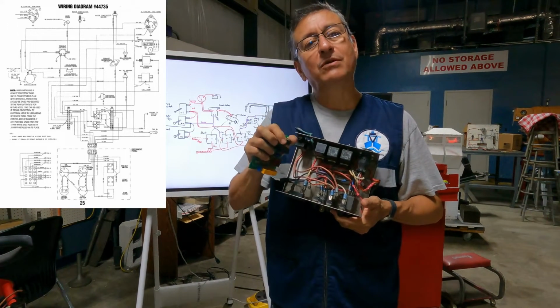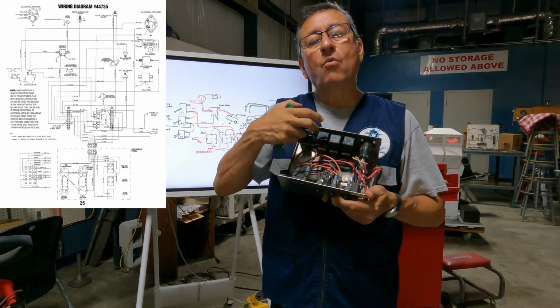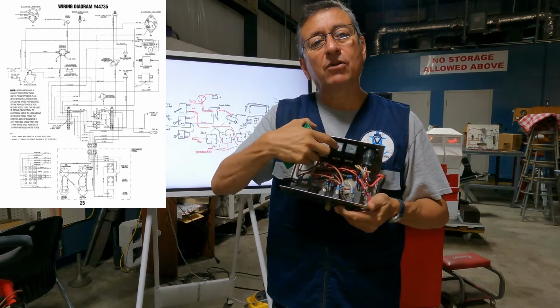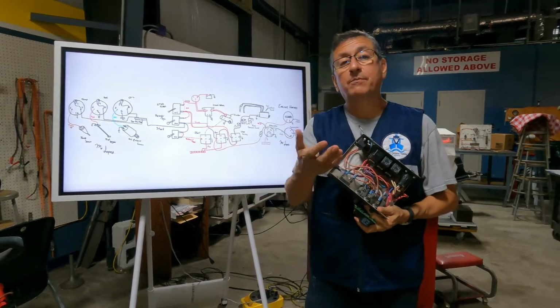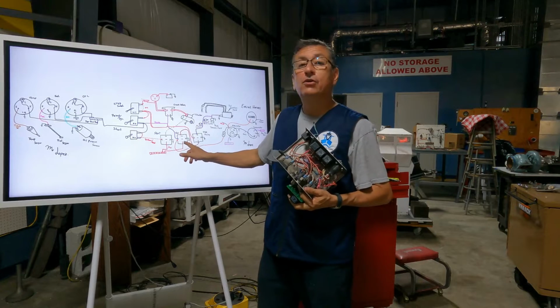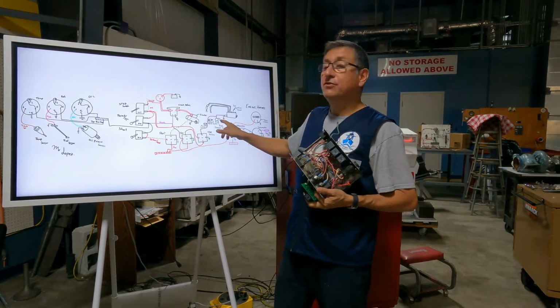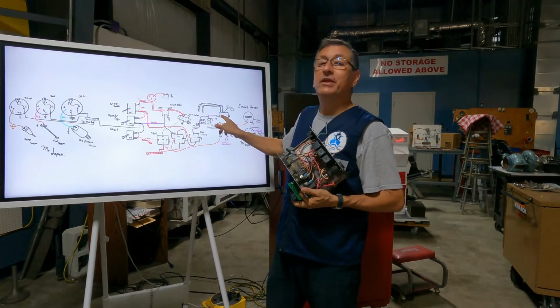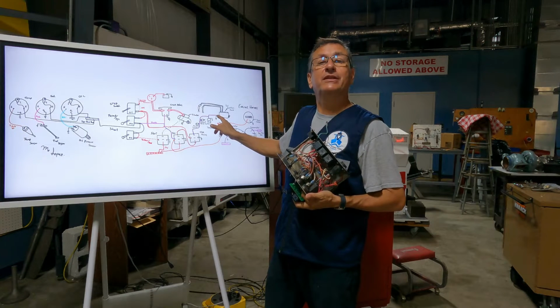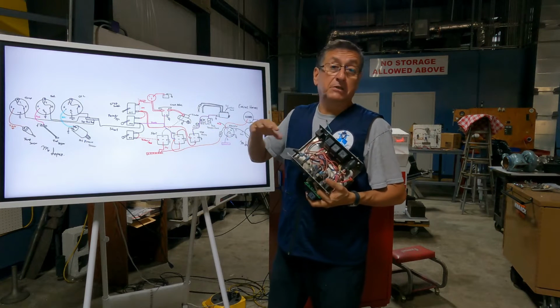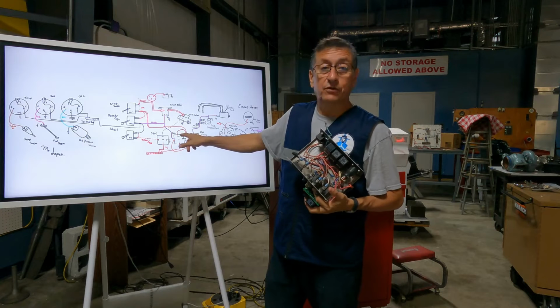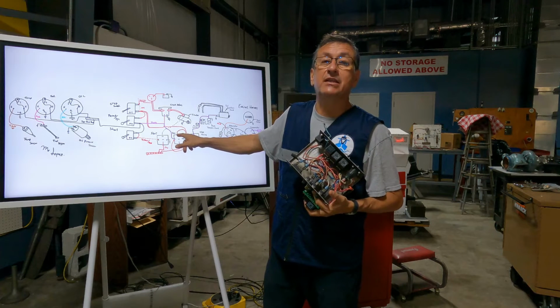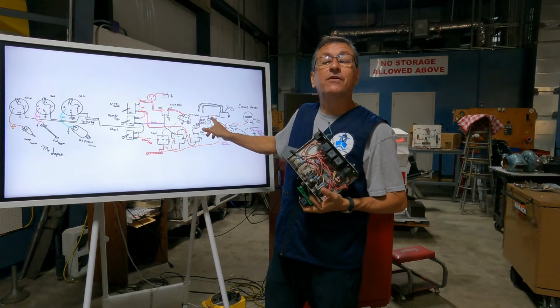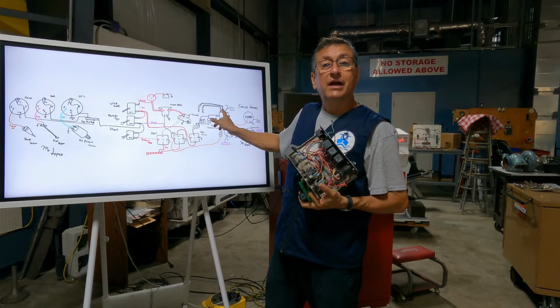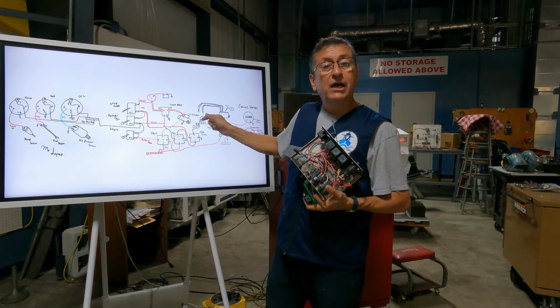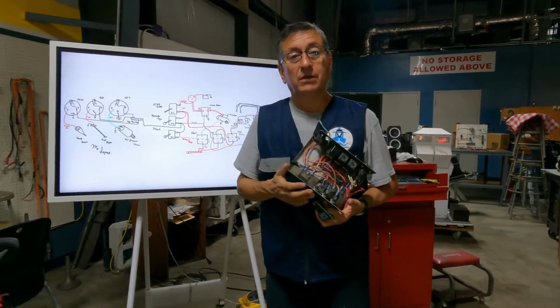Follow cable by cable. Identify what happens if there is a problem in the run relay. Remember, the run relay controls the operation of the fuel transfer pump and the start-stop solenoid. If the run relay is broken, you don't have output from terminal AD7A in the run relay, the transfer pump stops, the start-stop solenoid closes, you lose fuel, and the engine stops.